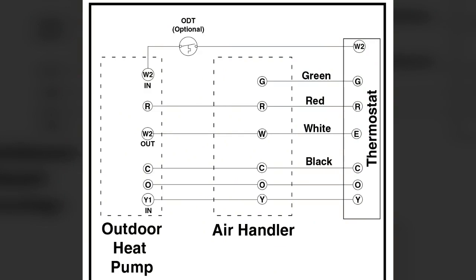Those are pretty standard common connections, so I'm not going to spend much time in this video about that, except for keep in mind that R and C has to go out to that heat pump at all times because you have to have 24 volts for that defrost board to work properly. The other thing I want you to keep in mind is the G and Y terminals of your air handler. Remember, G being energized on that air handler is only going to be for the fan speed. When you have a heat pump heating call or you have an air conditioning call, that Y terminal on the air handler has to be energized because that is your cooling speed. That's what sets cooling speed, not G.